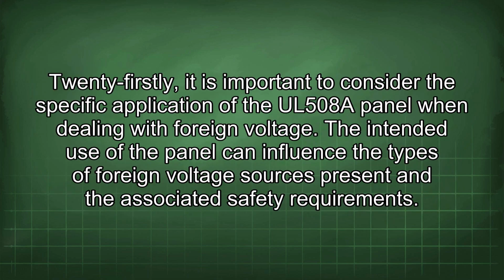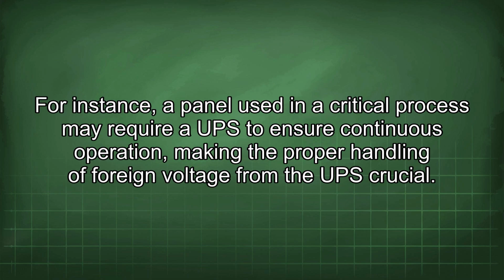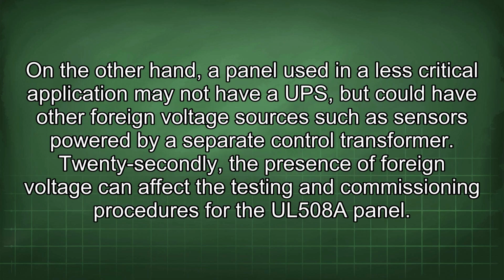Twenty-firstly, it is important to consider the specific application of the UL508A panel when dealing with foreign voltage. The intended use of the panel can influence the types of foreign voltage sources present and the associated safety requirements. For instance, a panel used in a critical process may require a UPS to ensure continuous operation, making the proper handling of foreign voltage from the UPS crucial. On the other hand, a panel used in a less critical application may not have a UPS, but could have other foreign voltage sources such as sensors powered by a separate control transformer.